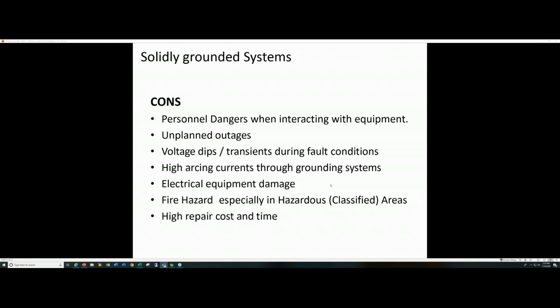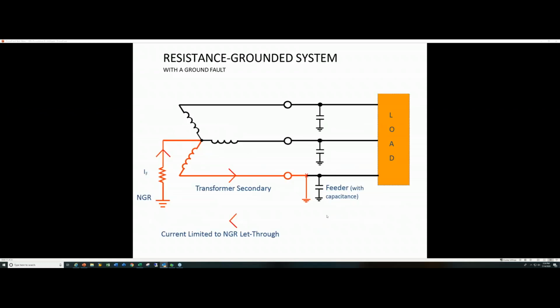I've seen it when we had a fault in our bus system and had a poorly grounded breaker on a 15 kV breaker, poorly grounded. And the fault actually found another path over a roll-up door in the basement of a powerhouse that had bark buildup, and all of a sudden the bark caught on fire. So it's highly likely, if that were to happen, that you would have a fire. Even combustibles in the area would catch on fire if you had them in there. And the biggest thing is, of course, the personnel dangers, but also you have high repair cost and the time it takes to get back on your feet.